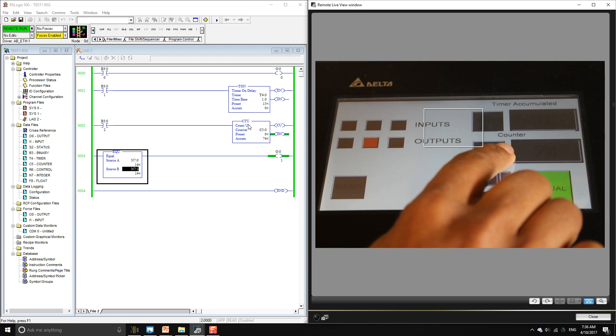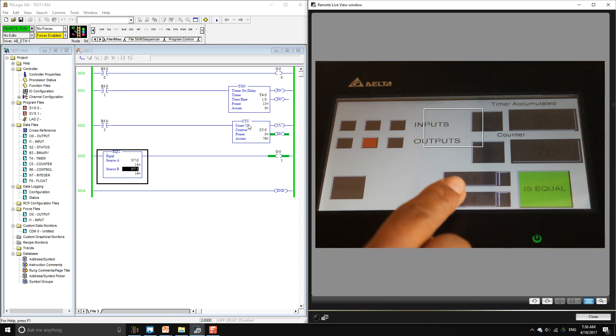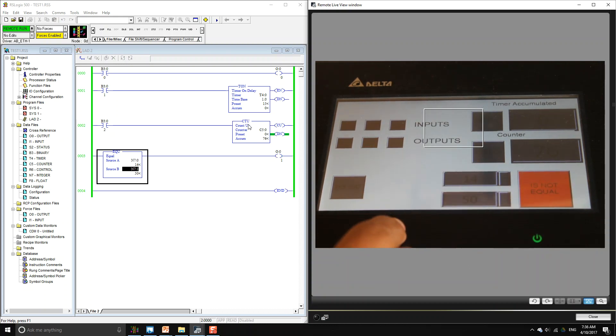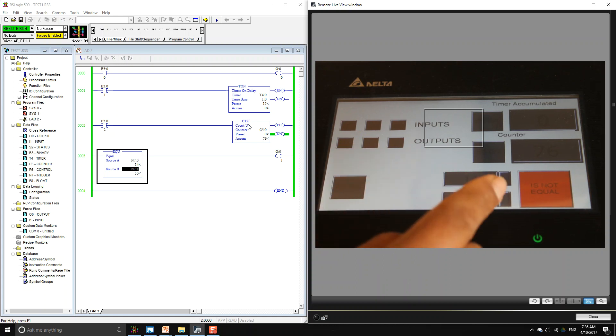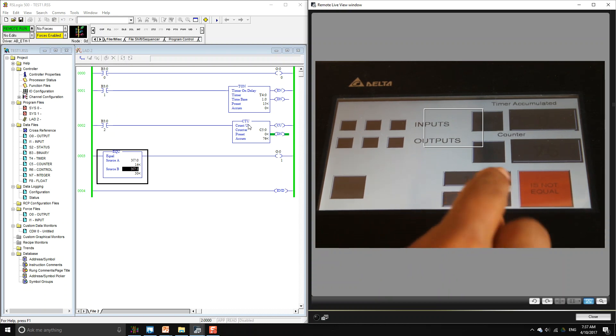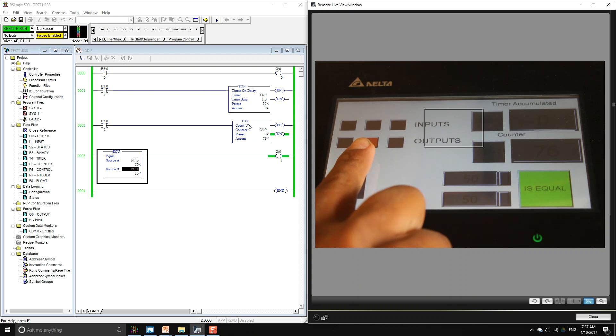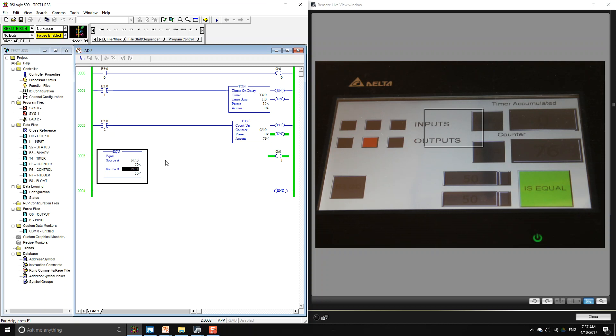We can start monitoring those counter values. For our integers, we can change the value of either integer. For instance let's change the bottom one to 50 — then output one goes off and the indicator shows they're not equal. If we change the top one to 50 as well, output one gets energized and the indicator shows equal, which is what we specified in this rung of the ladder logic.